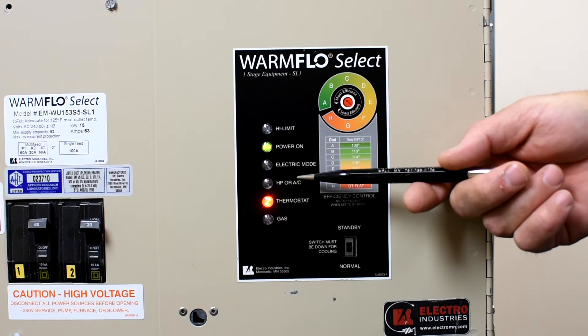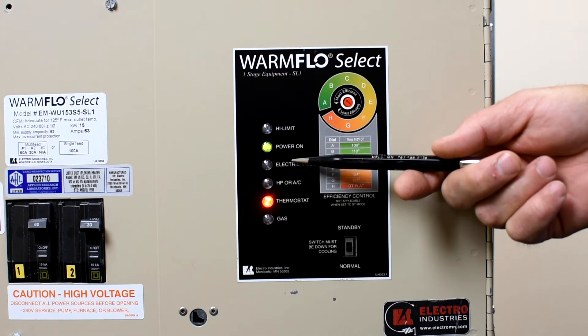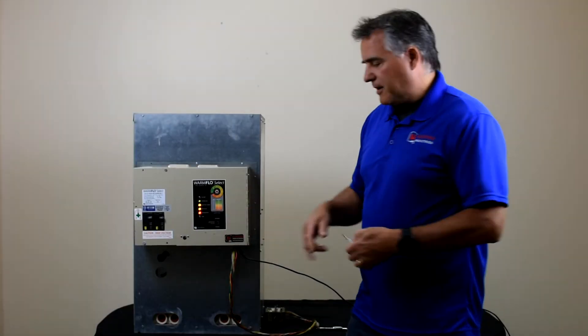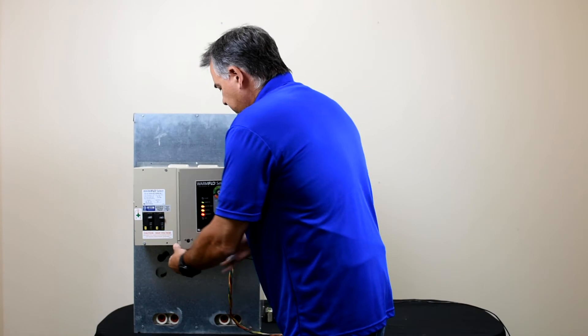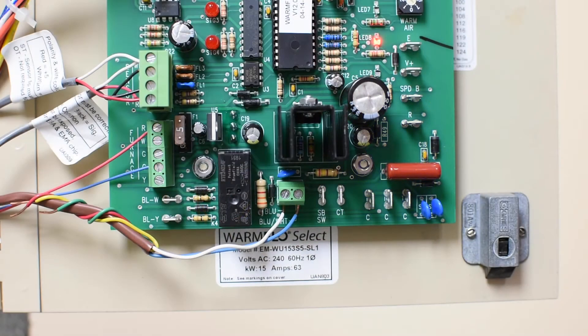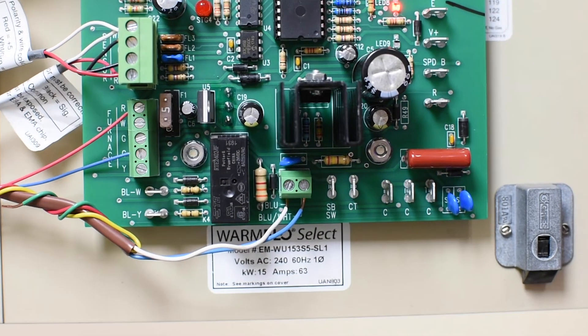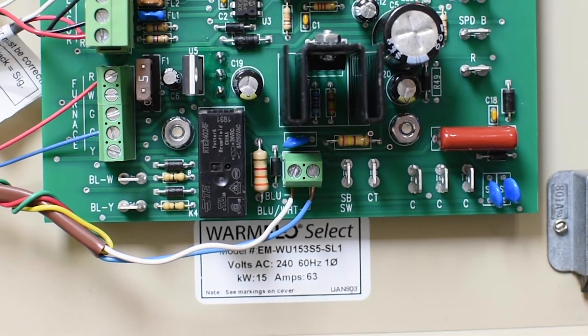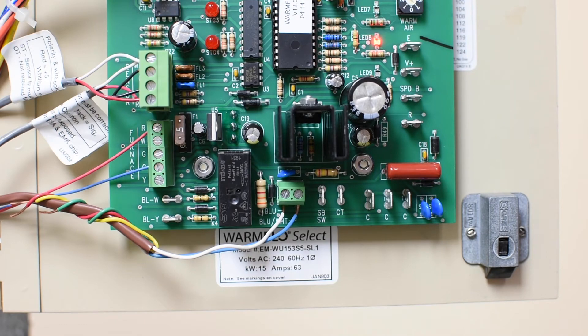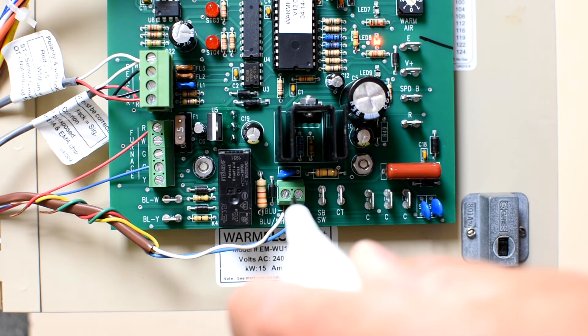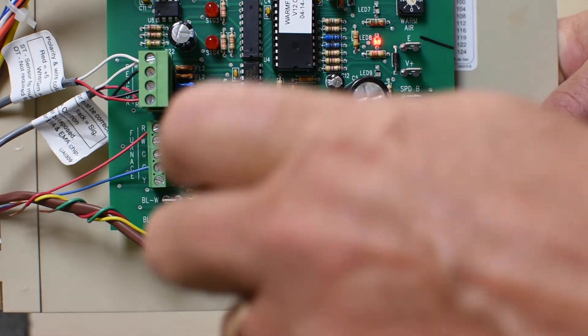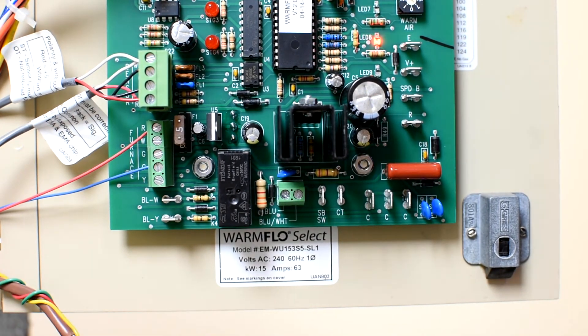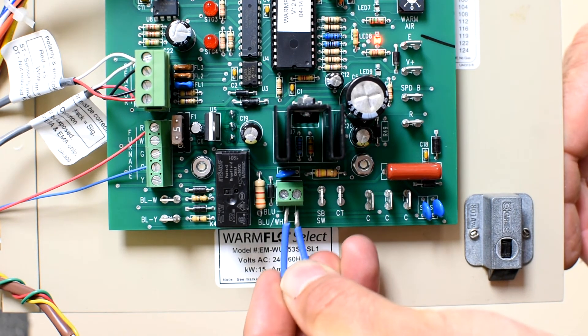If our electric mode light is off and our standby normal switch is in the normal position, the next thing we want to check is our utility control connections. When you open up the control board, you're going to find a terminal that's labeled blue blue white, and on some older versions, it'll actually be a blue and blue white wire. That circuit has to be closed for the system to go into cooling mode. If that system is open, that means that the power company or utility is doing a control. What we can do is temporarily bypass that circuit—just pull the two wires off and place a jumper in there.